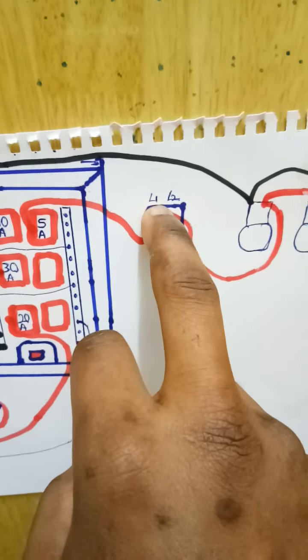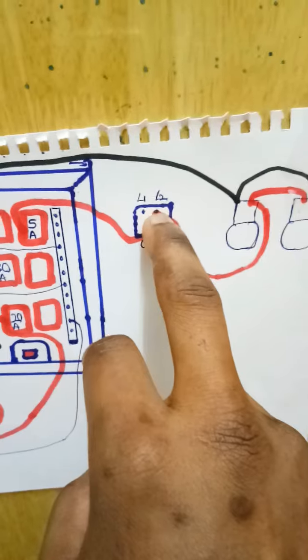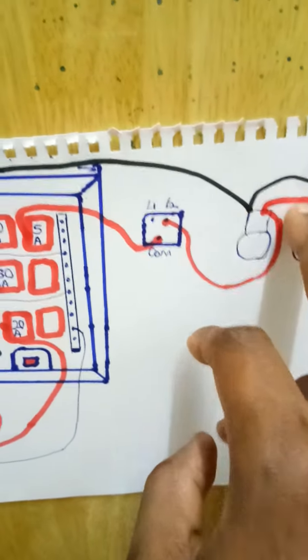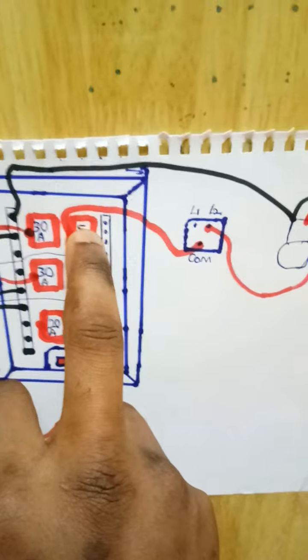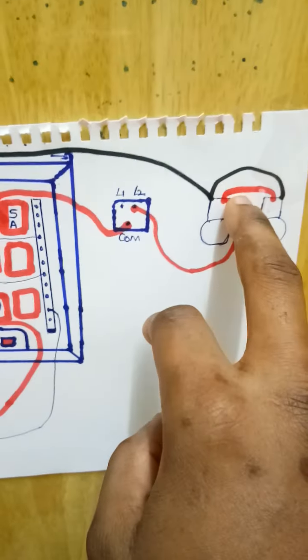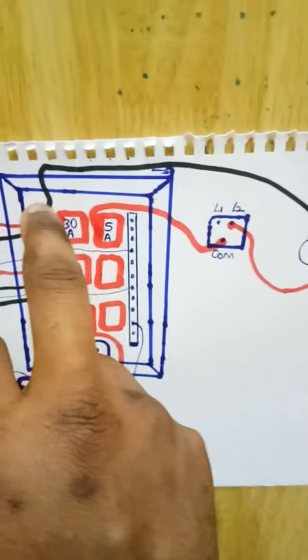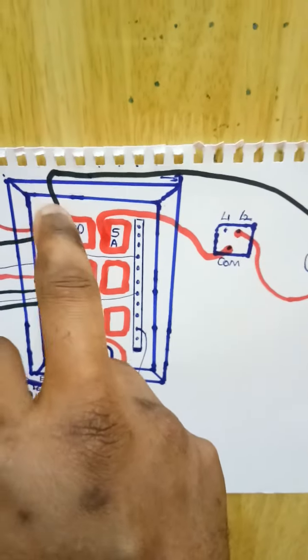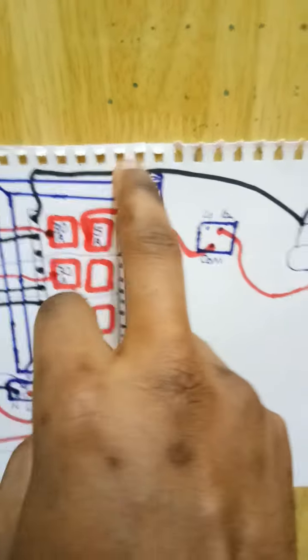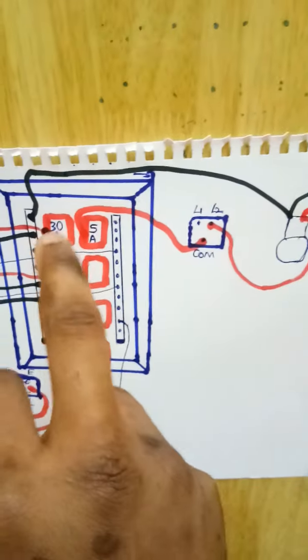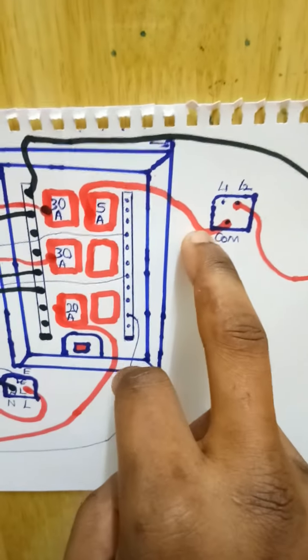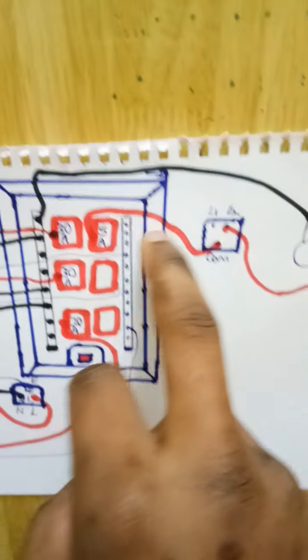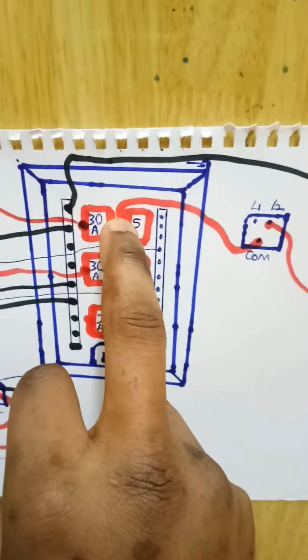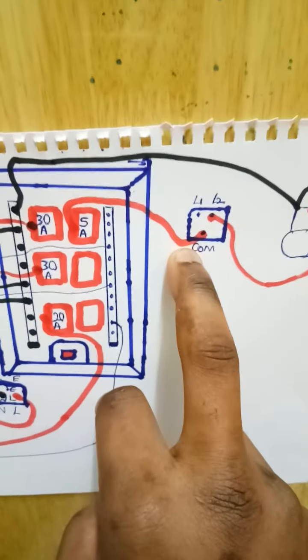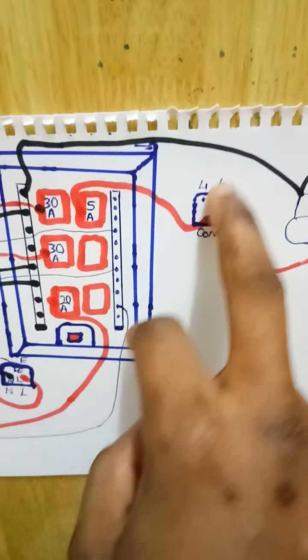So as you can see, from this point you connect to the lighting points. So in switches, the neutral doesn't come to the switches. The neutral goes directly from the distribution board to the lighting points. The live wire will always come to the switch first. The live wire comes from the distribution board to the switch, and from the switch you can now connect to the lighting points for one circuit.